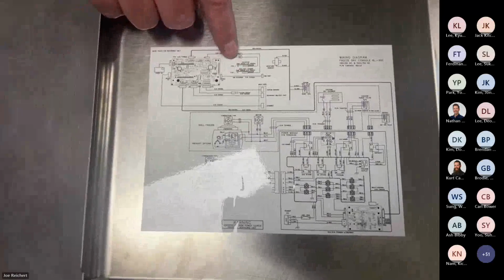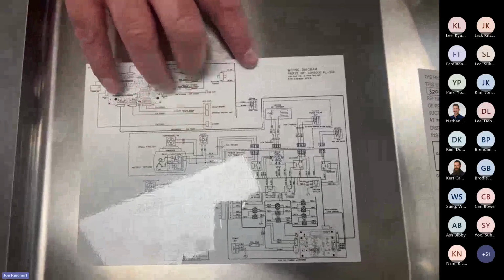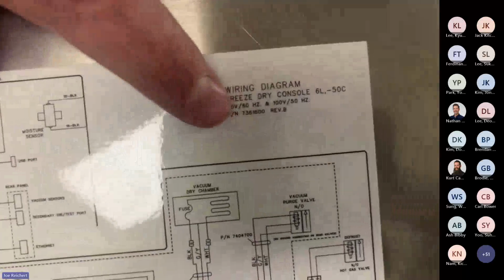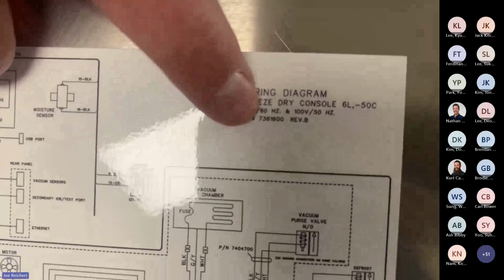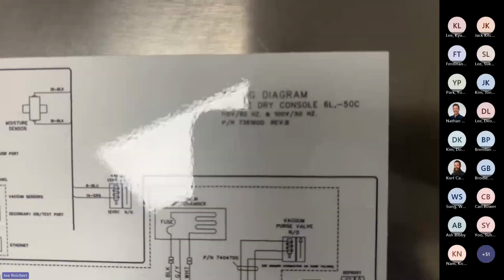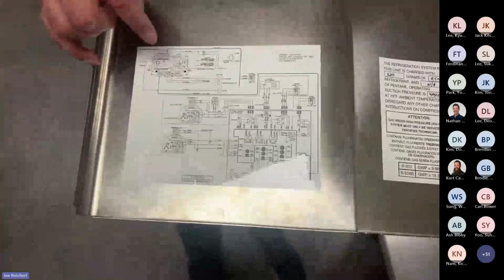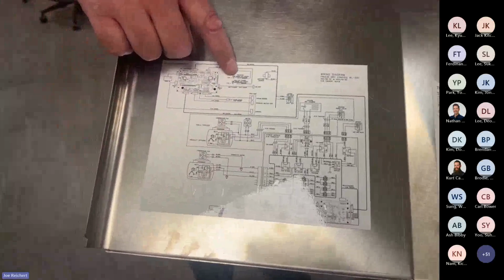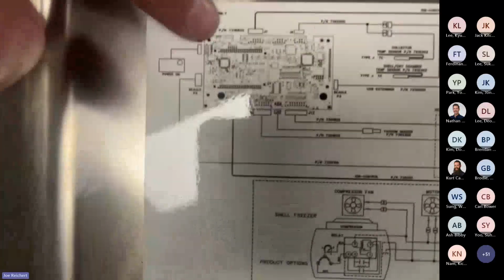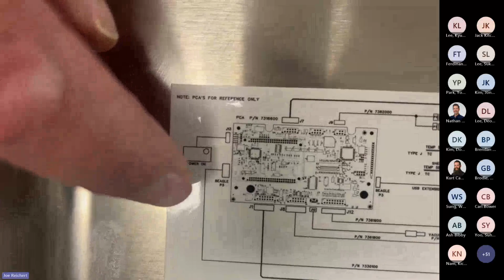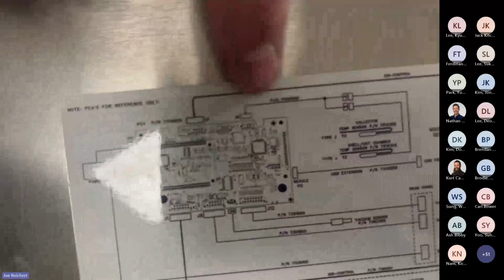On your wiring diagram, the print is fairly small. If you have issues trying to see it, there is a part number right here on all of our wiring diagrams. So if you tell us what unit it is, we can find the wiring diagram. But if you give us this part number, we'll be able to go right to it, and we can email you a normal size wiring diagram so you can zoom in and see it a little bit better. It does give you some helpful part numbers in here for your temperature probes and your vacuum sensor. It tells you your PC board part numbers. It's really hard to see in these small prints, but some of your harnesses also have part numbers. So if you need a harness, or something became disconnected, then we can get part numbers directly off your wiring diagram.